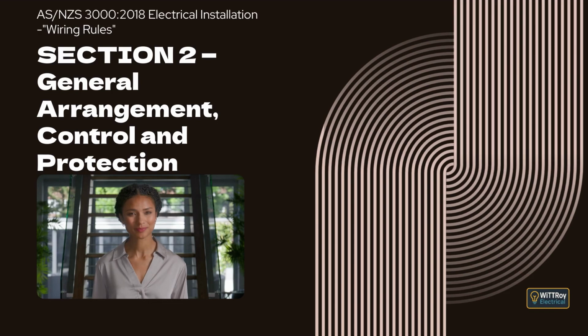Clause 2.5.1.3 Submains and final subcircuits. This clause covers overcurrent protection for all subcircuits within the installation. Overload and short-circuit protection must be installed at the origin of every circuit. Protection must also be added at places where the cable becomes smaller or has a reduced current carrying capacity. There are a few exceptions.